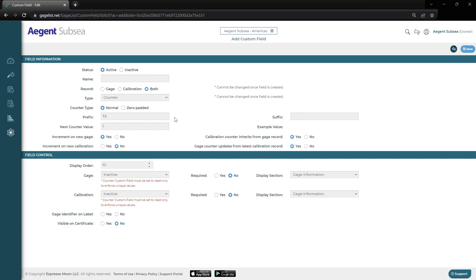This is a great alternative to the gauge-list ID. Down below, we can choose the display order, and the read-only, edit, or inactive options. We could also make the field required, and we can choose the display section in which this appears, both on the gauge and calibration record. We can also choose to make it visible on our certificate — if we want new fields or information on our certificates, we can select yes to add that. We could also make it a gauge identifier on a label.